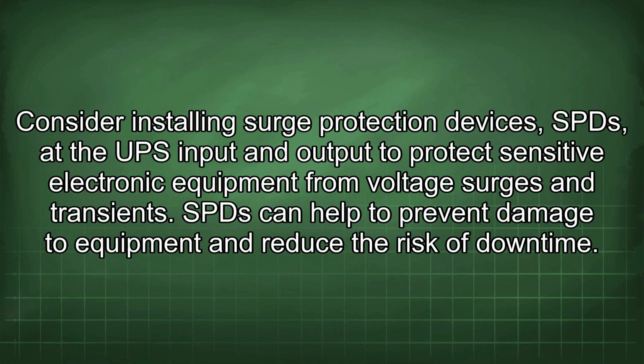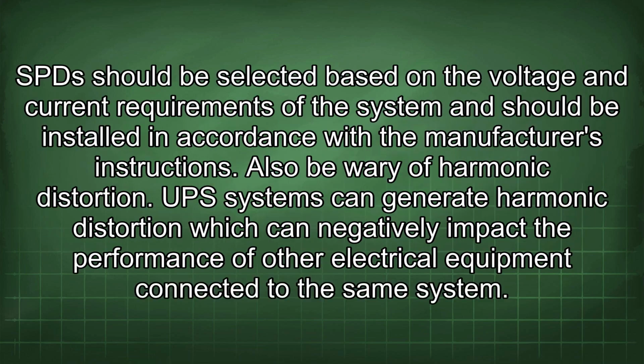Consider installing surge protection devices, SPDs, at the UPS input and output to protect sensitive electronic equipment from voltage surges and transients. SPDs can help to prevent damage to equipment and reduce the risk of downtime. SPDs should be selected based on the voltage and current requirements of the system and should be installed in accordance with the manufacturer's instructions. Also be wary of harmonic distortion.